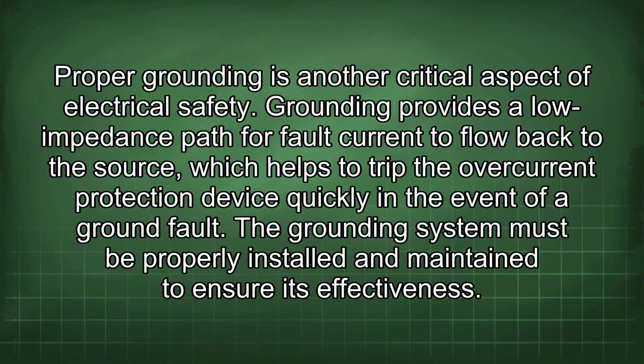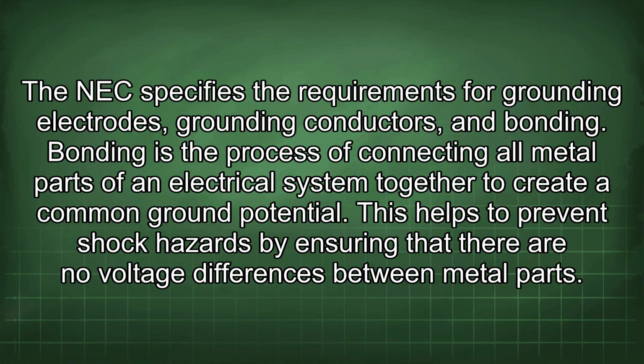Proper grounding is another critical aspect of electrical safety. Grounding provides a low impedance path for fault current to flow back to the source, which helps to trip the overcurrent protection device quickly in the event of a ground fault. The grounding system must be properly installed and maintained to ensure its effectiveness. The NEC specifies the requirements for grounding electrodes, grounding conductors, and bonding.